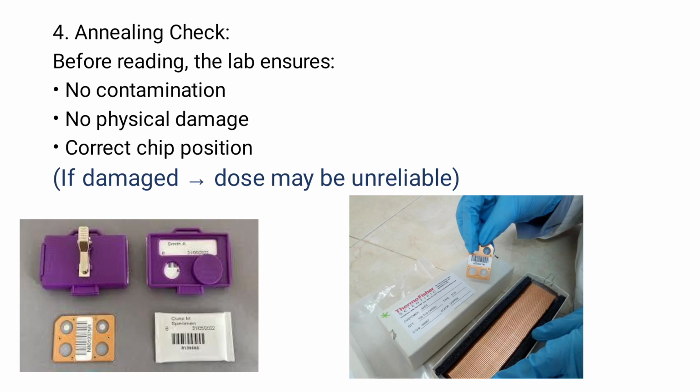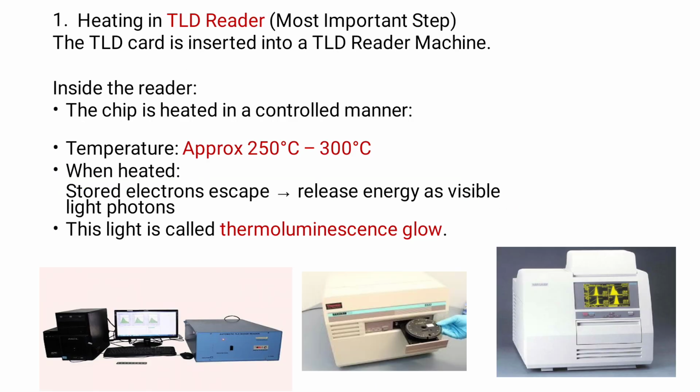So before reading, the lab ensures that there is no contamination, no physical damage, and correct positions of the chips. If any damaged batches are there, that is unreliable and they are kept aside. The next step is heating in the TLD reader.